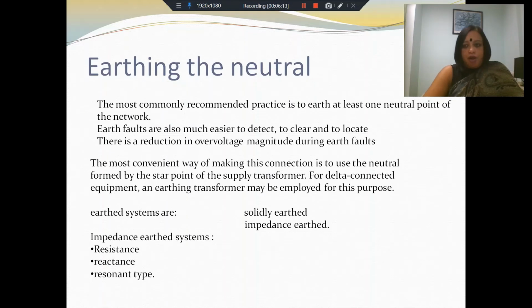The most common way of earthing any system, as I have already mentioned, is by earthing the neutral. The advantage of earthing the neutral is that if there are any earth faults, and the neutral is earthed, it is easier to detect the faults and to clear and locate the fault. Also, during earth faults, earthing the neutral will reduce the overvoltage that can happen. The fault overvoltage that comes across the system is automatically reduced when you have the neutral grounded. So therefore, apart from earthing, we are also able to address the issue of fault location, fault clearing, and the overvoltage due to fault just by earthing the neutral.